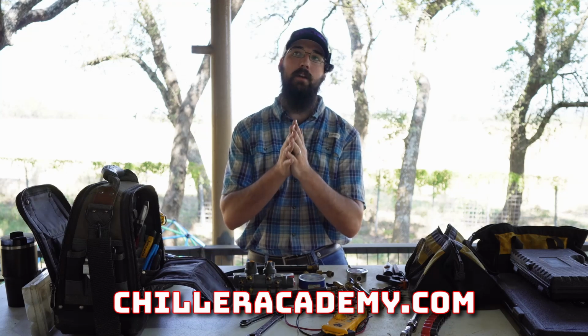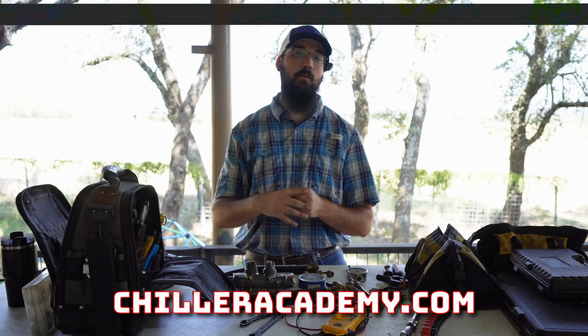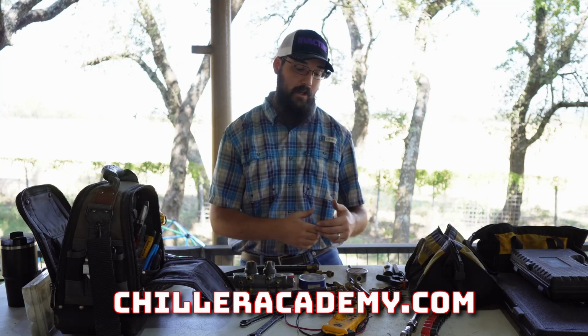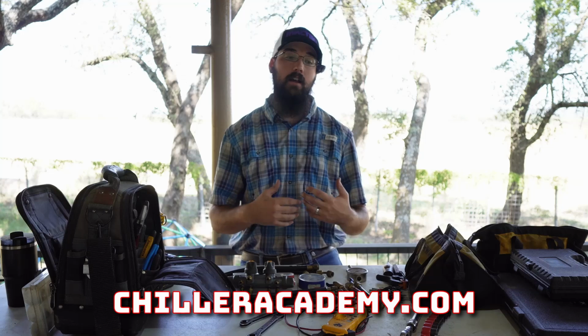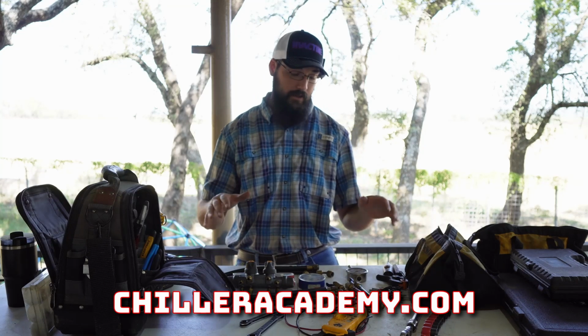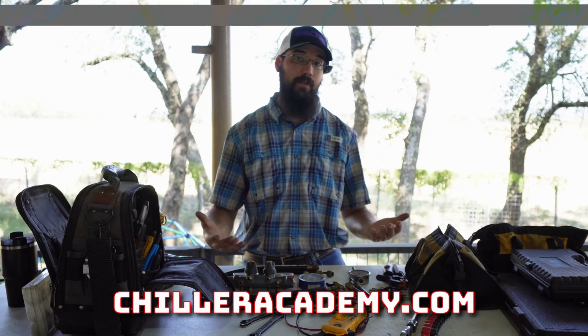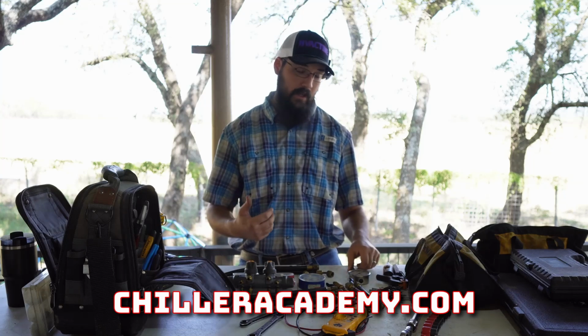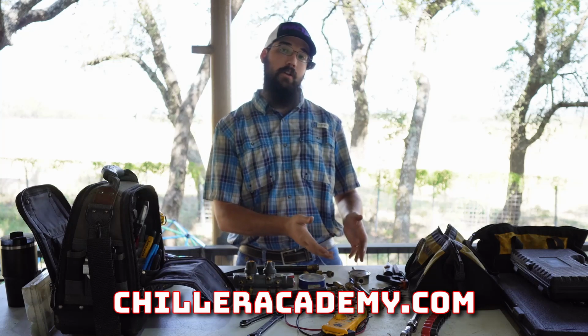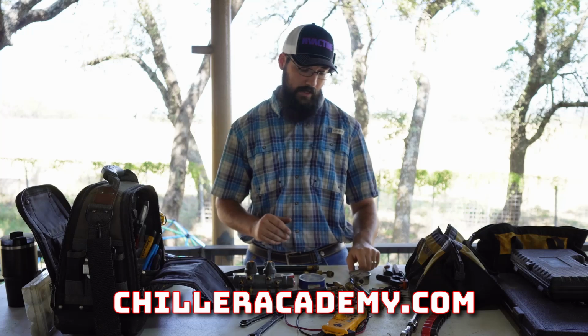What I would suggest is best for you, look at what is the highest end of the normal pressures you usually see. You may be working at facilities routinely that never see above 100 psi. At that point, invest in a set of 0 to 100s. That way you're covered. I routinely saw systems that were running 100, 150 psi for a lot of the work I was doing in downtown Austin, so I needed that 200. So you need to figure that out for yourself and then make the best decision you can.